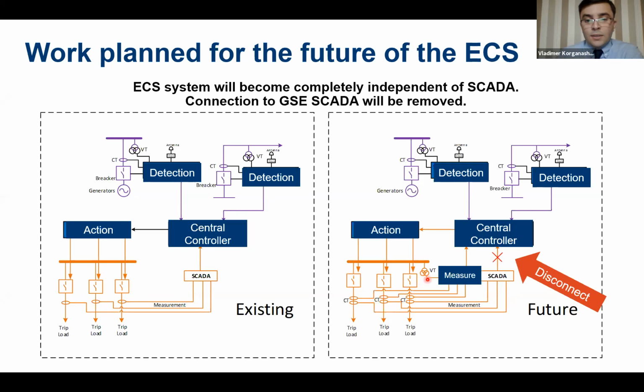Vladimir, go ahead. Yes, as of today, centralized ECS depends on the SCADA system. There are cases when the SCADA system is lost. It means that the central ECS is out of service or out of action. That is why we want to make ECS completely independent. So in the future, we are going to replace the measurements which are coming from SCADA to ECS. We need to install an independent device. After that, we will disconnect SCADA from ECS and add new measurements for ECS to make the ECS system completely independent.